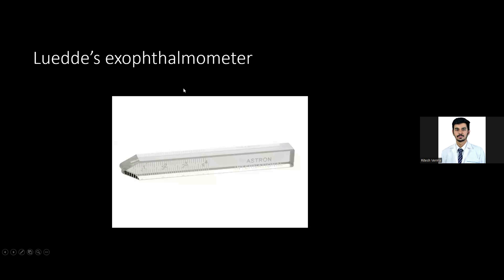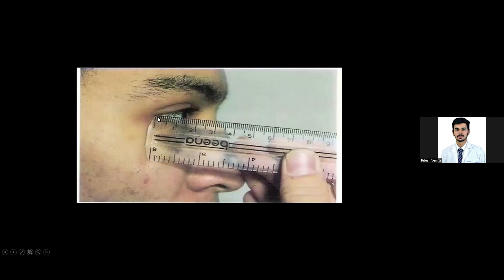The Luedde's exophthalmometer is one you may be asked to use in the exam because it does not require a lot of manipulation. This triangular edge goes to the lateral orbital margin. You place a scale at the lateral orbital rim and hold the ruler so that it bisects the cornea at its center — that is your reading. A difference of more than 2mm between both eyes indicates proptosis.